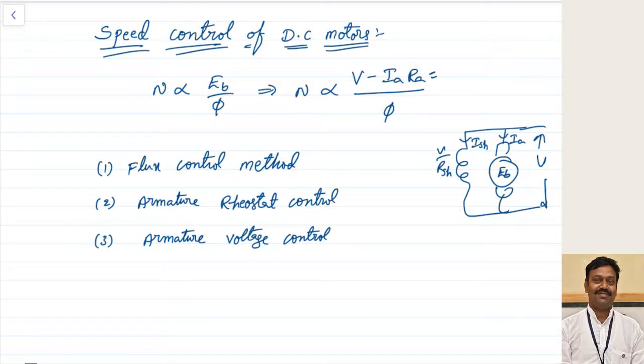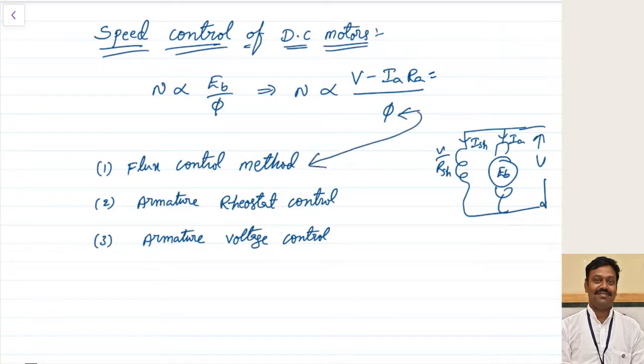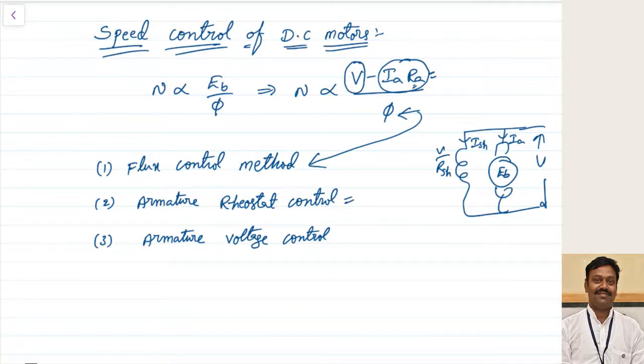The flux depends on different parameters for different machines. By controlling any one of these parameters, we can control speed. First, we can control flux — that is the flux control method. Second, we can control the Ia×Ra drop by inserting resistance — that is the armature control method. Third, we can change the supply voltage applied across the armature — that is also called armature control. So these are the three techniques.